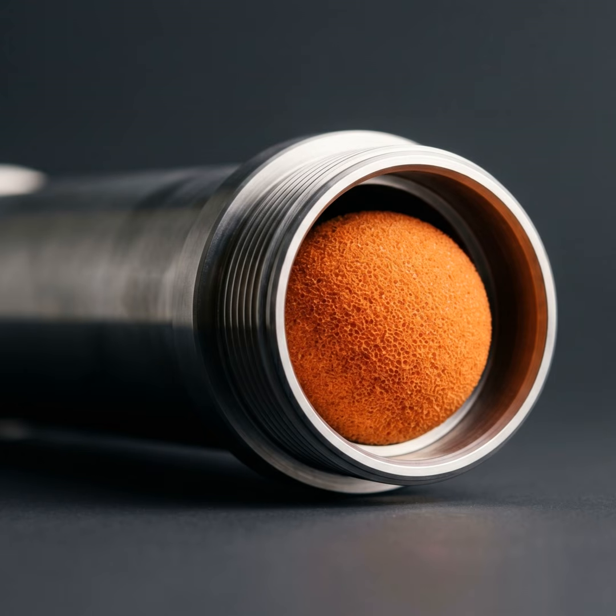Okay, so we've thoroughly covered the two highly technical halves of this deep dive. The basement and the roof. Right. Down in the hidden basement, we have the automatic tube cleaning system, the ATCS, continuously circulating slightly oversized orange neoprene sponge balls to wipe away precipitating mineral scale. Right. This completely eliminates the insulation trap, restoring perfect thermal conductivity. And crucially, it entirely eliminates the need for human maintenance workers to handle dangerous, life-threatening acid. Solving the human chemical hazard. Yes. Then, up on the roof, we have variable frequency drives, VFDs, constantly reading the atmospheric wet bulb temperature and dynamically adjusting fan speeds based on the affinity laws to eliminate psychrometric ignorance. And solving the thermodynamic waste.